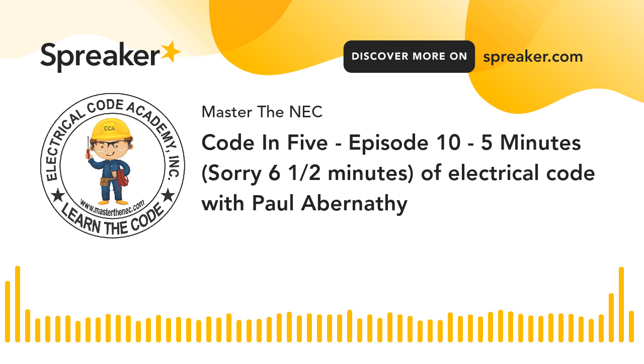Okay. Now, number 3 is the one that me and you deal with the most, because typically you might have a receptacle that's rated 60/75, and you might have an overcurrent device that's rated 60/75. So I'm going to use the 75. Now, granted, those conductors that are terminating on it might fall within the 14 to 1 gauge or 100 amps or less. However, because of number 3, here's what it says. It says conductors with a higher temperature rating, thus the 90 degree C, for example, if the equipment is listed and identified for use with such conductors.